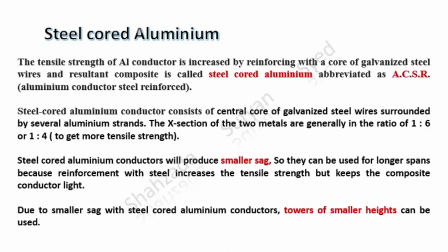And to overcome this issue, to overcome the low tensile strength of aluminium conductor, they are reinforced with a core of galvanized steel, and the resultant composite conductor is known as steel cored aluminium, abbreviated as ACSR, which means aluminium conductor with steel reinforcement.